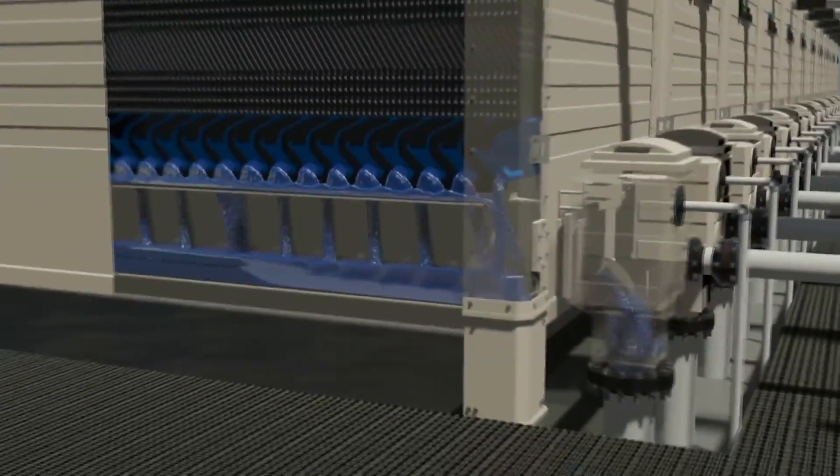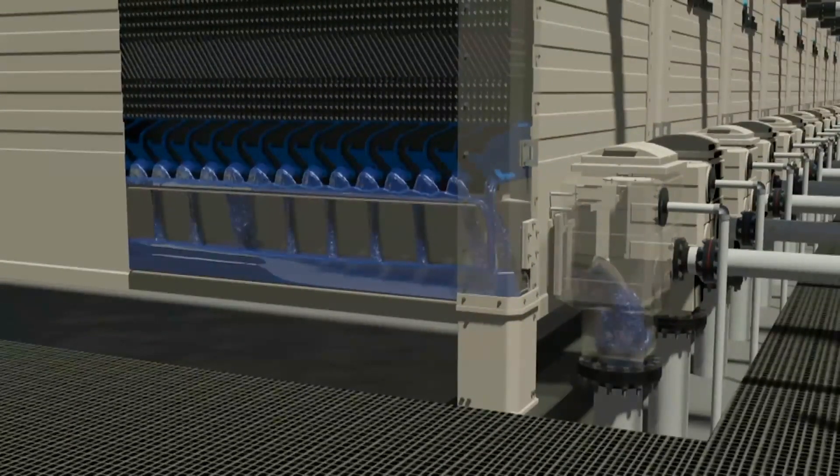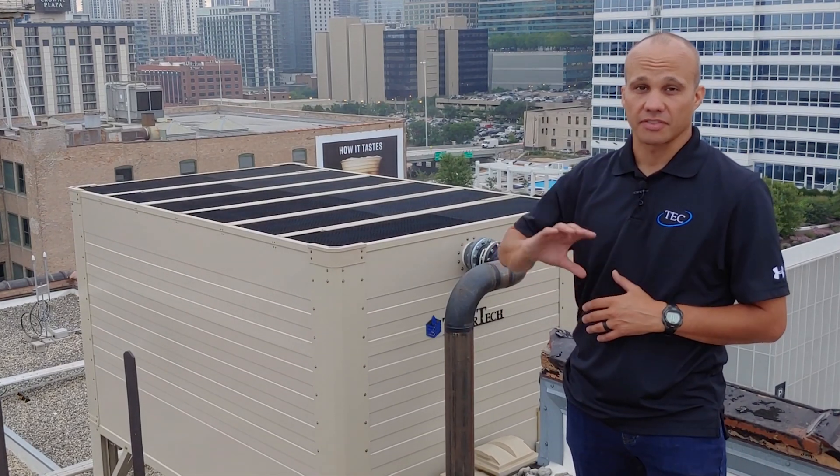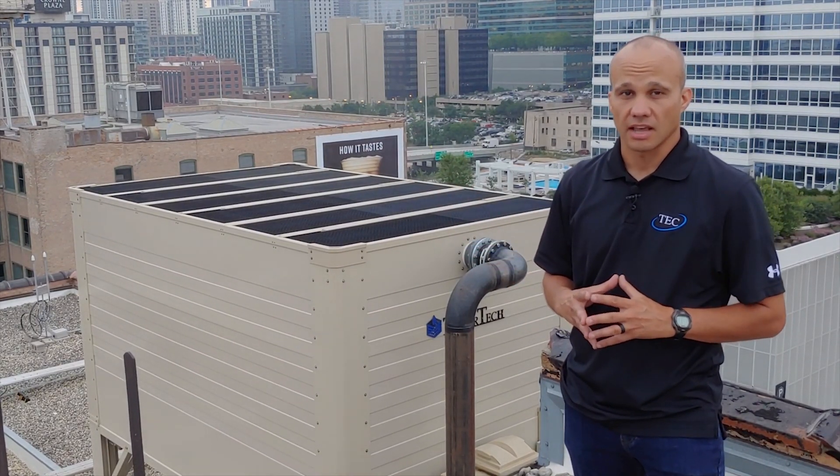After the water enters the fill media it drains down into the water collection system. It drains off to the side — it can't go straight down because that's where the fans are. It moves at a pretty high velocity, and the faster the water moves, the less likely it is for stuff to grow in there. Everything in this system is contained — we're not really open to the atmosphere, so less debris, dirt, leaves, bugs, and everything will get into the water. That allows us to reduce blowdown and increase cycles of concentration. As you can see, there's absolutely no water dripping out of the bottom and completely dry above, which is a health benefit as well.